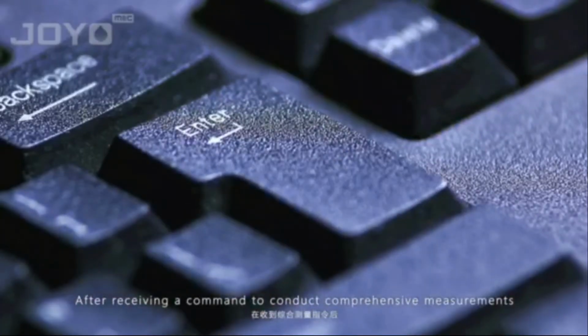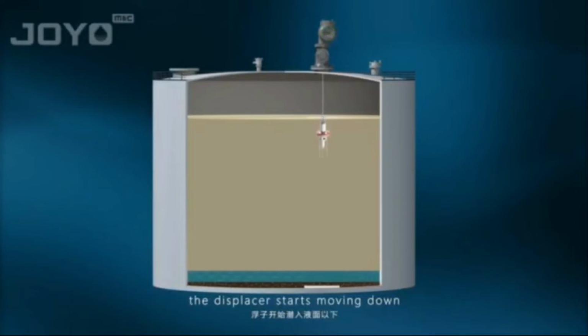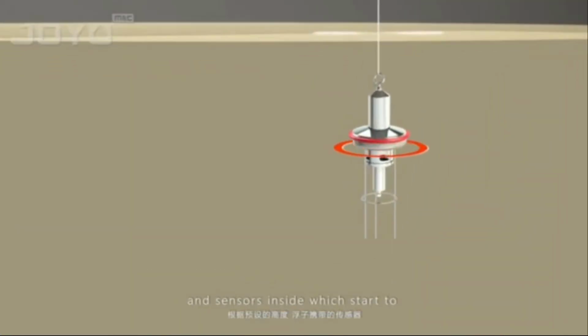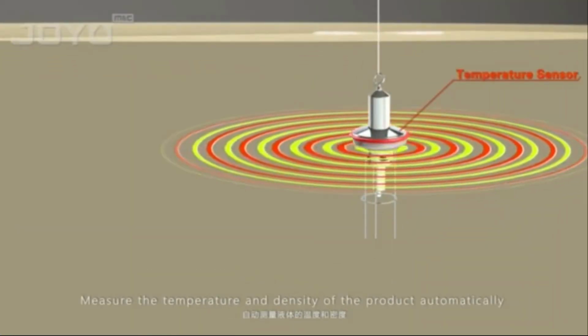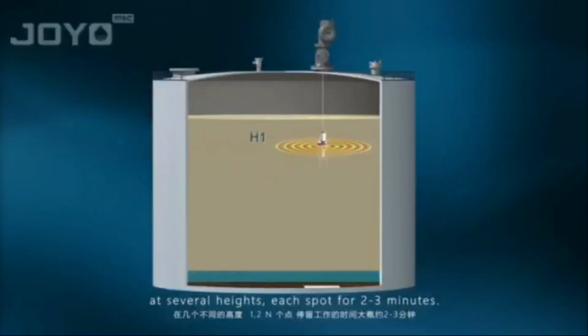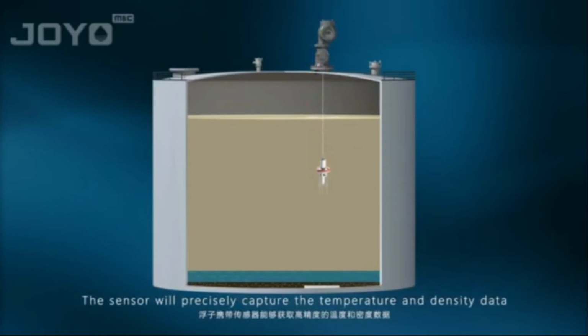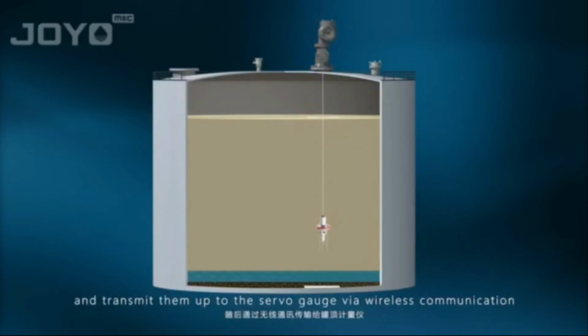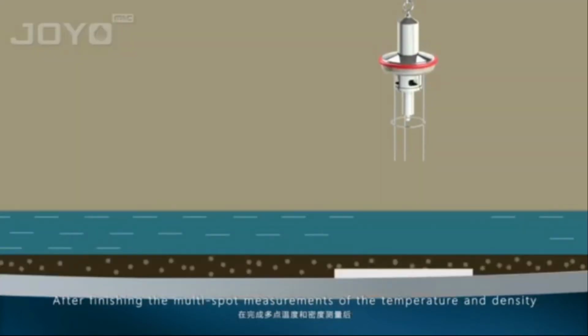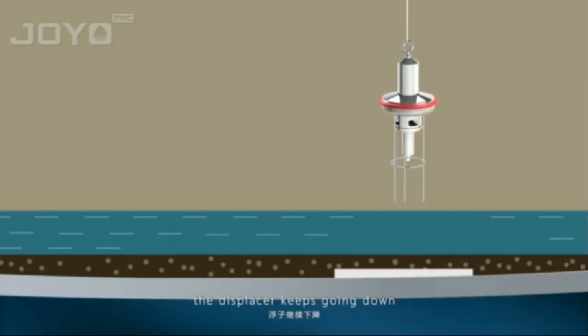After receiving a command to conduct comprehensive measurements, the displacer starts moving down, and sensors inside start to measure the temperature and density of the product automatically at several heights, each spot for 2 to 3 minutes. The sensor will precisely capture the temperature and density data, and transmit them up to the servo gauge via wireless communication. After finishing the multi-spot measurements of the temperature and density, the displacer keeps going down.